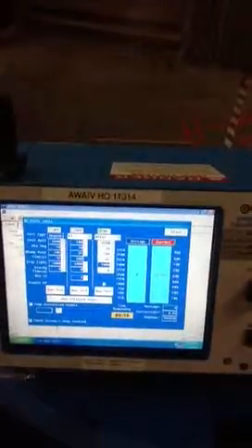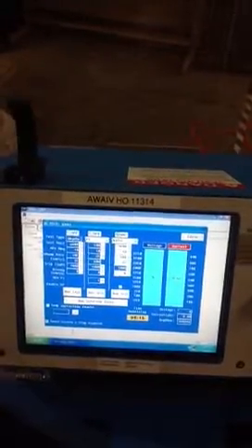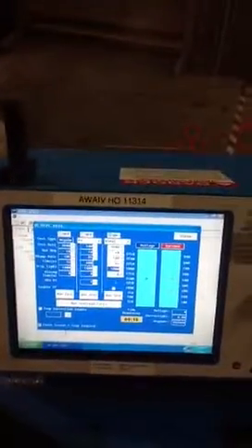Then we will open up the DC tests, and here we can select the voltage we want to apply to the motor. This is the minimum mega ohms that we're going to perform, that we will pass fail on. This is how fast we will ramp up the voltage, and here would be the time that you're going to hold. For this video, I'm going to hold it at only 15 seconds. This would be your trip levels, and all of my high pot settings are set now.